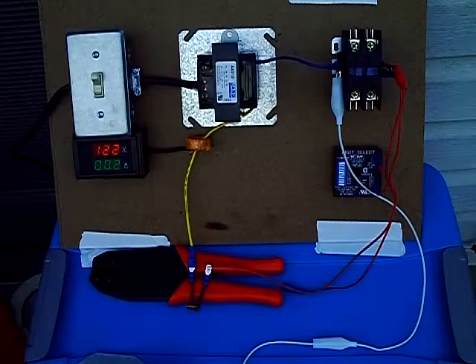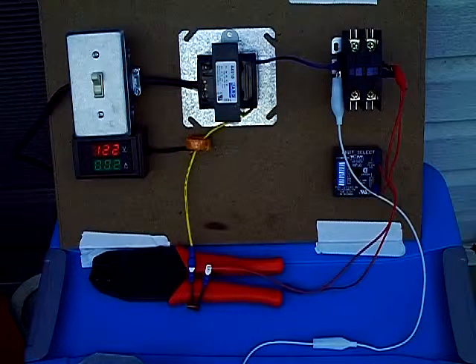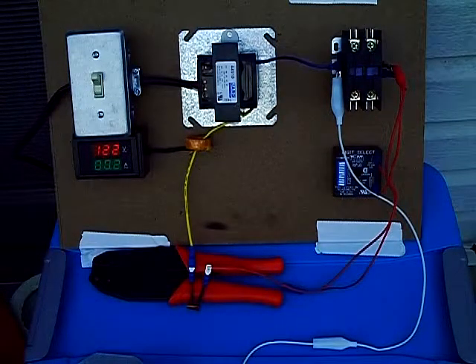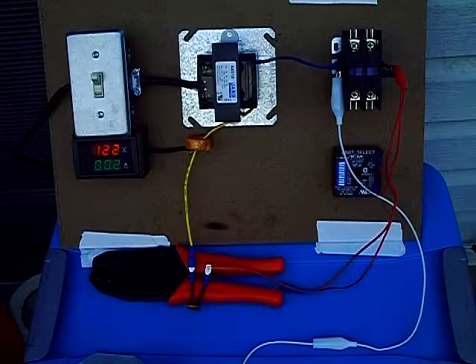Now it can trip the resettable fuse a couple different ways. It can be like a traditional type of protection, where when it blows or opens up, it'll stay in a lockout mode, still protecting and opening the control voltage circuit until the service tech gets there to locate the short. It can be wired in to do that.